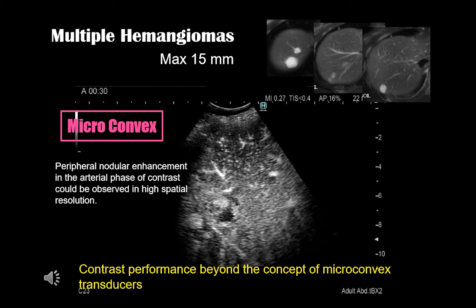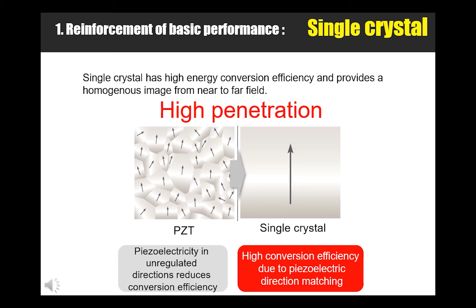One of the technologies that achieve the high image quality of C23 is the use of a single crystal on a microconvex probe. This has enabled us to obtain a solid signal to the depths, with high energy conversion efficiency. Acoustic pressure is one of the most important requirements for ultrasound imaging. Conventional microconvex probes, including those of other companies, could not raise MI to above 1 because they heated up when the radiated acoustic pressure was increased.